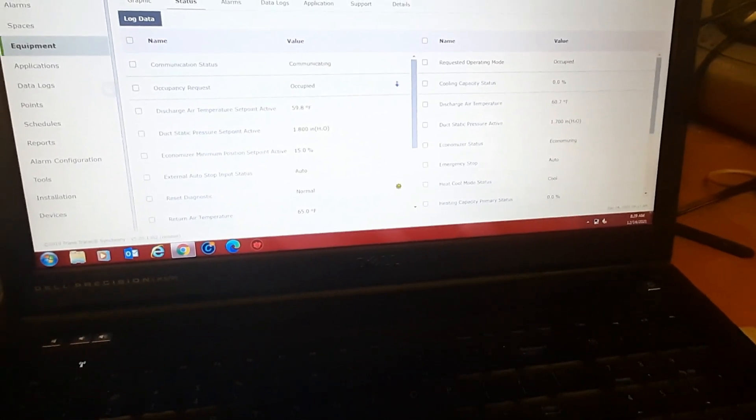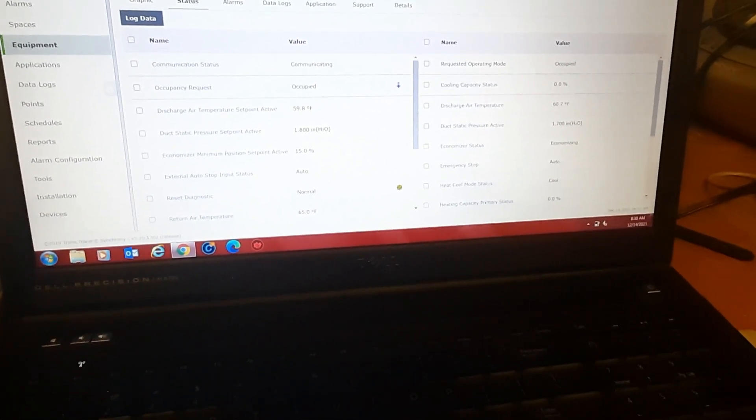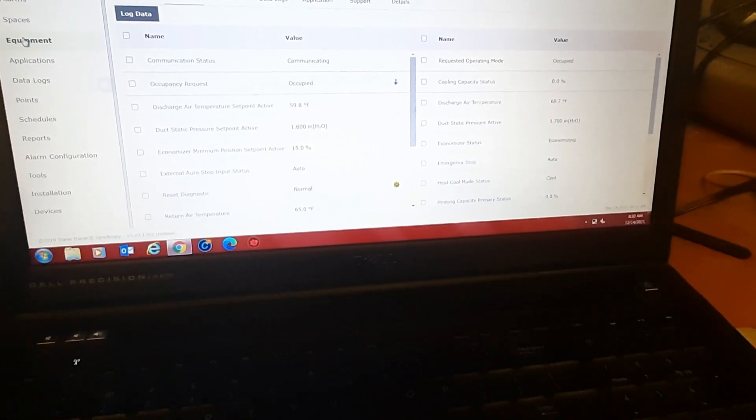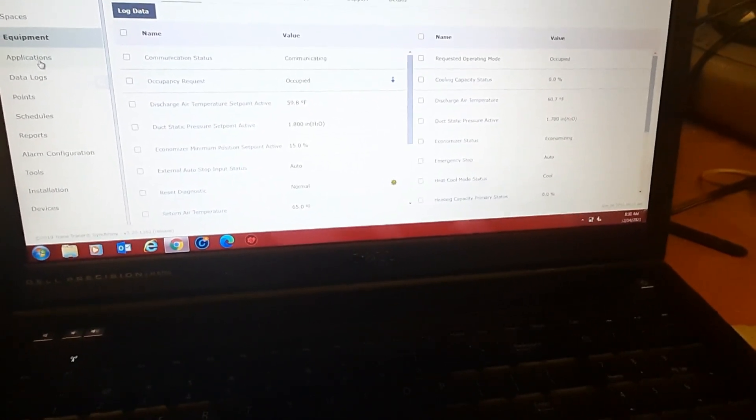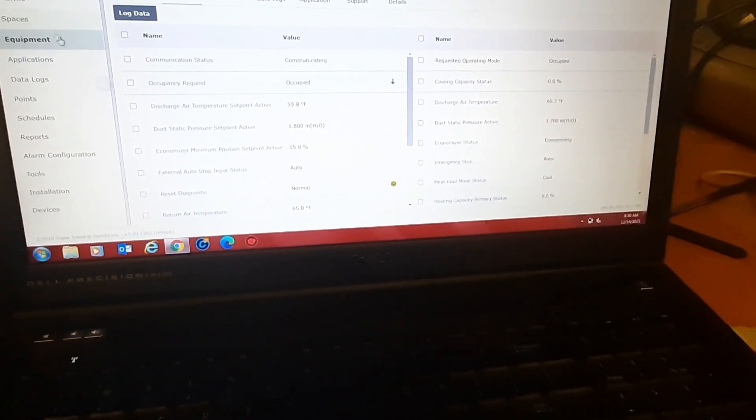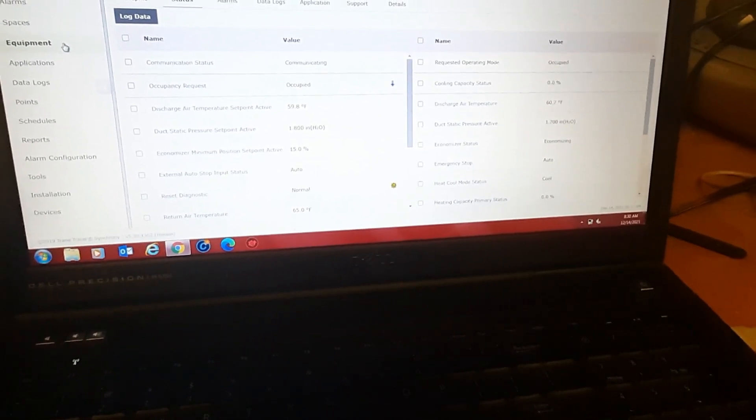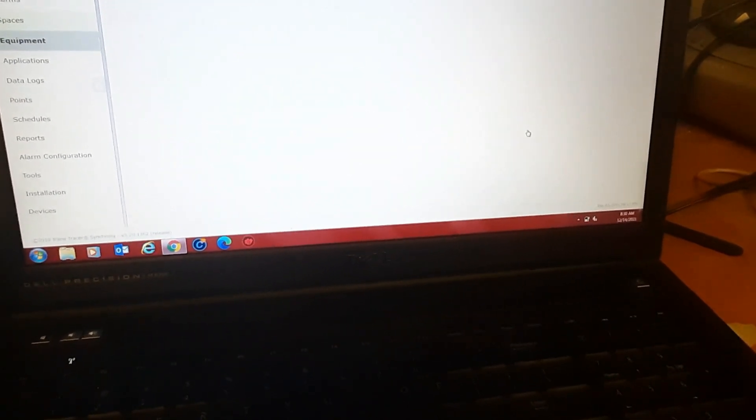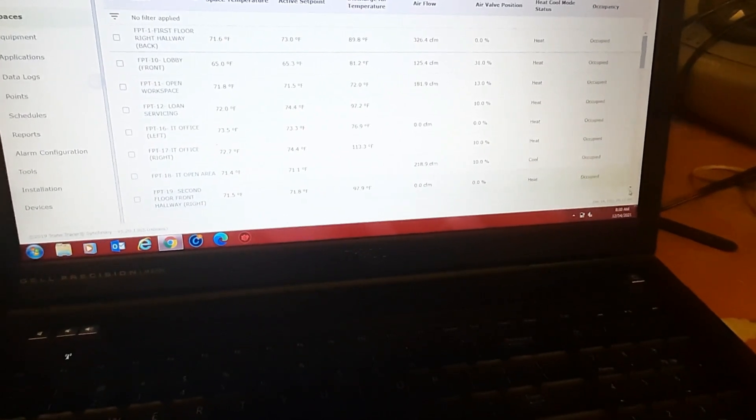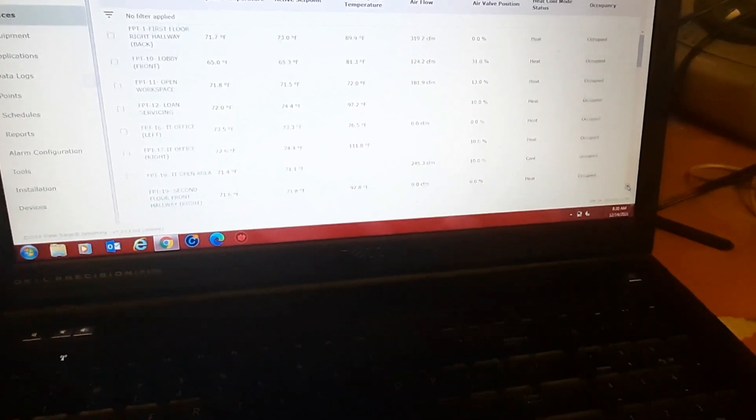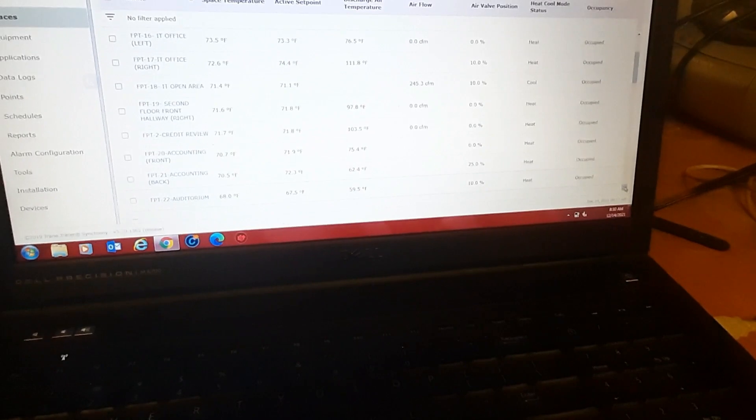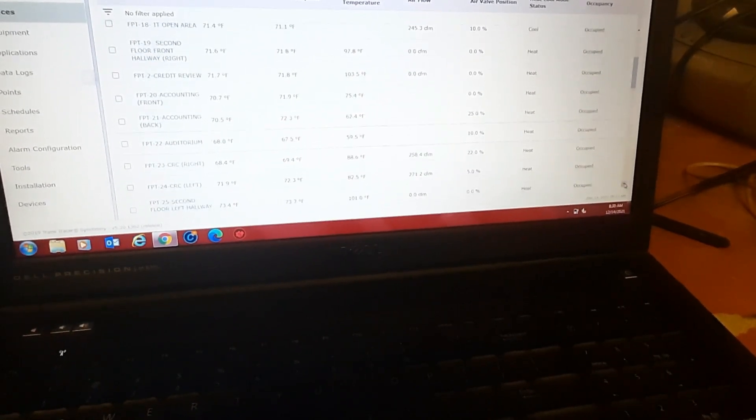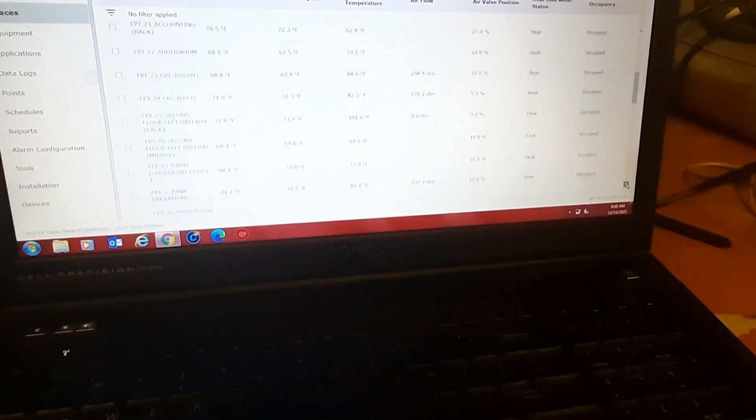We will go into a morning warm-up and a daytime warm-up if they're enabled. So instead of going to the IntelliPak rooftop, because it's doing what it's supposed to and we've got no alarms, we need to stick with our VAV box because each VAV box or FPT box, fan powered terminal, has an electric heat strip.